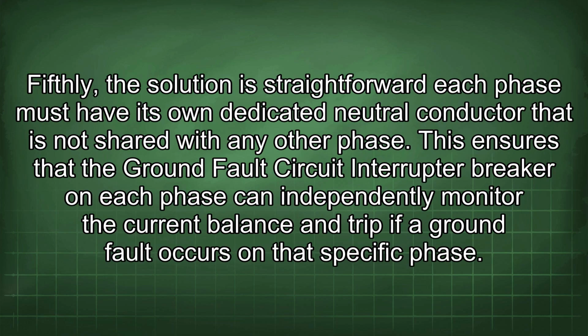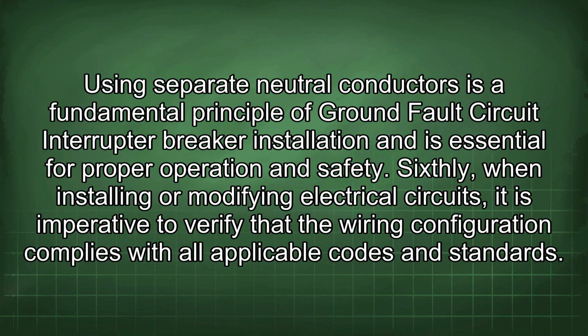Fifthly, the solution is straightforward. Each phase must have its own dedicated neutral conductor that is not shared with any other phase. This ensures that the ground fault circuit interrupter breaker on each phase can independently monitor the current balance and trip if a ground fault occurs on that specific phase. Using separate neutral conductors is a fundamental principle of ground fault circuit interrupter breaker installation and is essential for proper operation and safety.